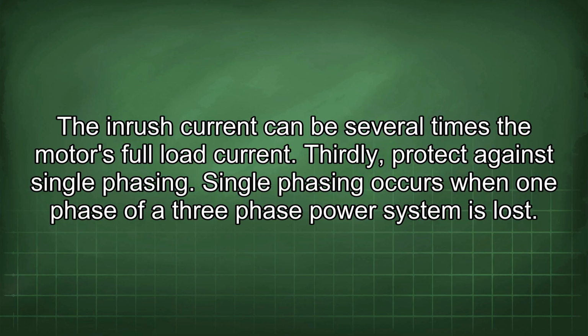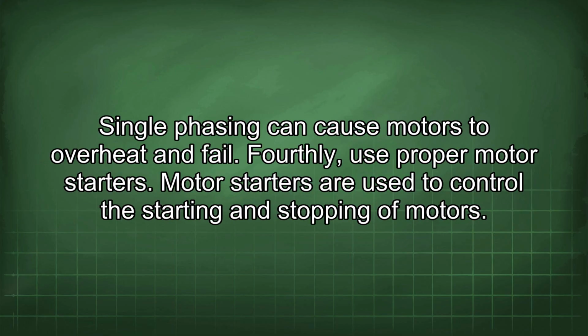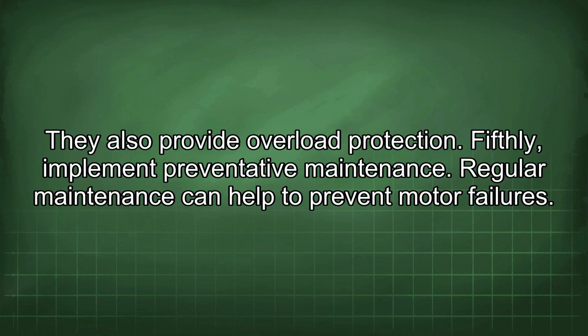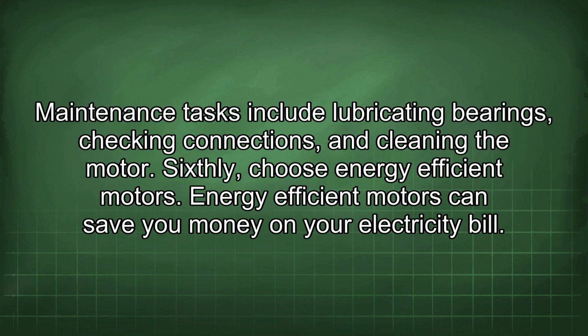Thirdly, protect against single phasing. Single phasing occurs when one phase of a three-phase power system is lost. Single phasing can cause motors to overheat and fail. Fourthly, use proper motor starters. Motor starters are used to control the starting and stopping of motors. They also provide overload protection. Fifthly, implement preventative maintenance. Regular maintenance can help to prevent motor failures. Maintenance tasks include lubricating bearings, checking connections, and cleaning the motor. Sixthly, choose energy-efficient motors. Energy-efficient motors can save you money on your electricity bill.